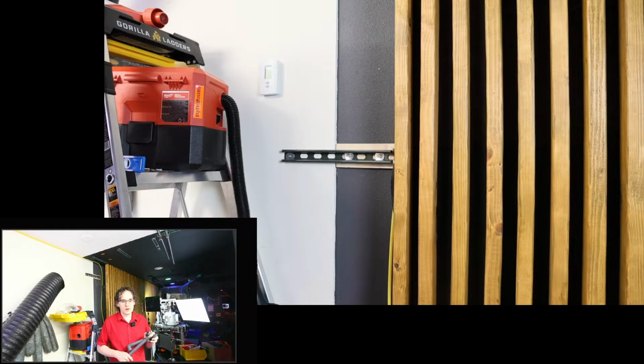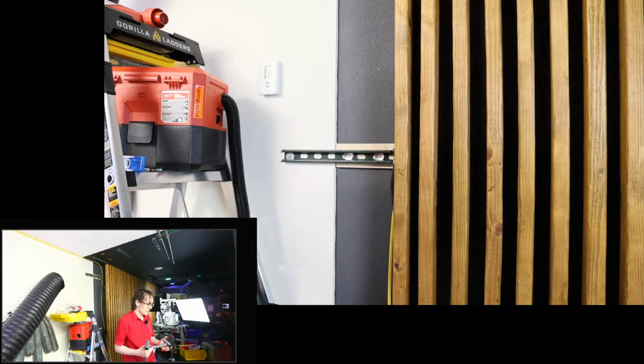And the turbo pump temperature is a software-based interlock, I think, actually, but the pump has another way. If the pump actually stops pumping, then the hardware vacuum controller will stop. But if the pump just gets warm, the software will eventually try to stop it. And if the turbo pump gets warm enough, the turbo pump itself will shut down, and then the vacuum controller will become aware of that immediately. The vacuum controller is FPGA based, so I guess you can kind of call it hardware. It's not really firmware. For the firmware, call it software, I think.